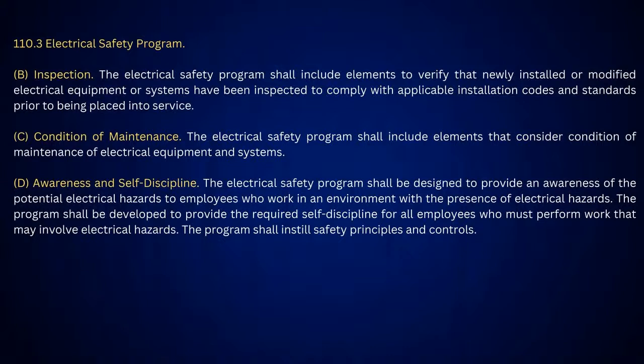So this is what it's talking about: making sure that if you have any modification, you're complying with applicable installation codes and standards. I would be looking at 70B also with this, because it tells you that if you did a modification and it didn't increase it, and in 5 years you add some more, then every 5 years you at least have to check to make sure that the available fault current is what's listed on the label, which is required. So I have a good example of this.